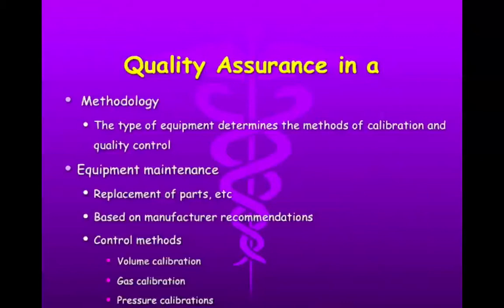Some of the maintenance that we have to do when these things go out of control is we might have to replace some parts. We might have to change some flow transducers. Sometimes manufacturers actually make us replace certain parts even if they seem to be working fine at certain time intervals. We have to have some control mechanisms, again, to make sure that when we're calibrating these things that they are calibrating accurately. And how do you do that? You test it. We use volume calibrations, a 3-liter syringe.